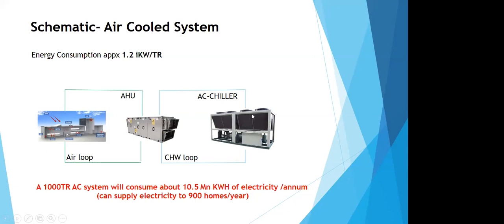But the problem with the air-cooled chiller is that it's consuming almost 1.2 kilowatts per ton, right? It is an energy guzzler. While the water-cooled chiller was consuming 0.6 kilowatts per ton, the air-cooled chiller is consuming something like double of it. It's almost 1.2 IKW per TR. So a 1,000-ton air-cooled system would consume almost 10 million kilowatt-hours of energy per annum. And that much energy can serve almost 900 homes. So we get rid of the menace of water, but we are caught in the menace of energy consumption. So now to bridge the gap, that's where the adiabatic coolers come into play.